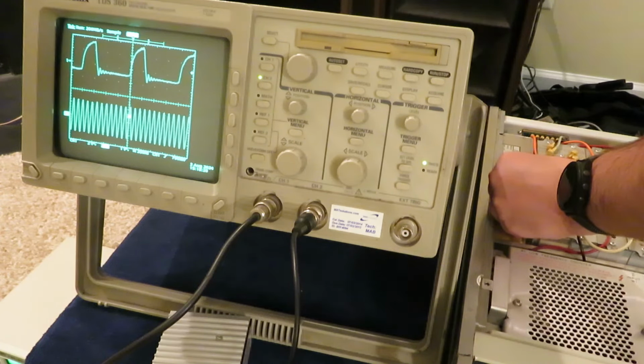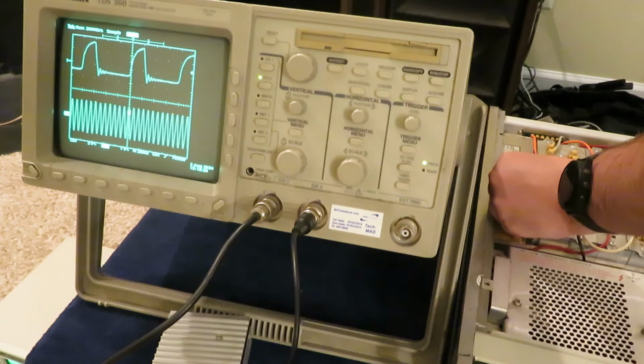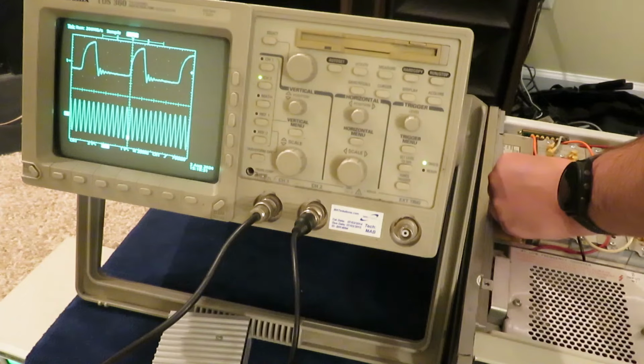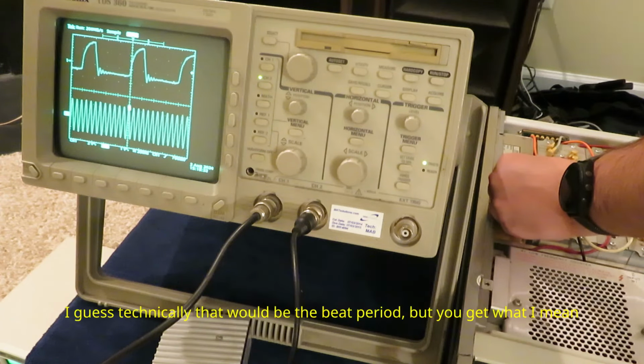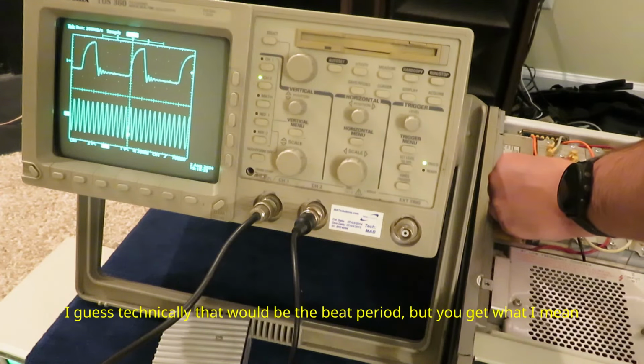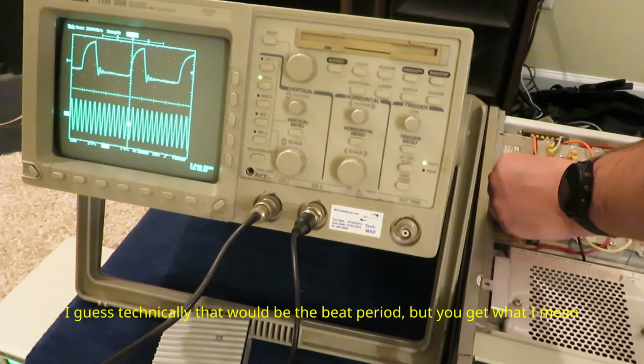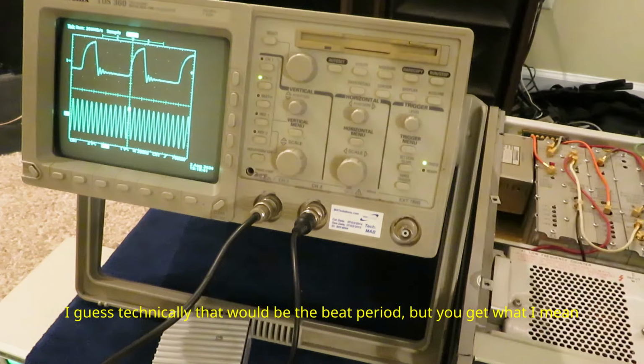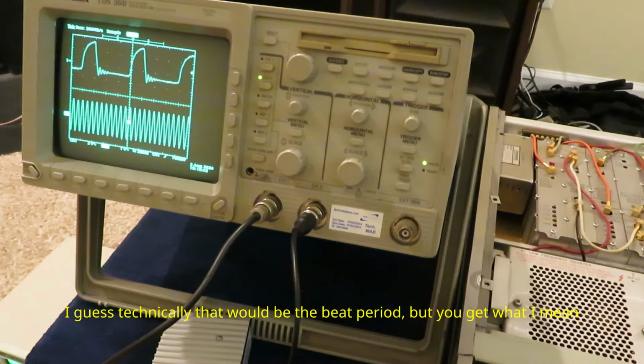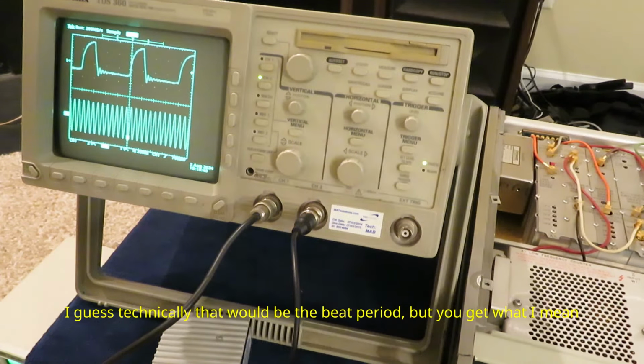So the test they recommend is, I think they said 5 seconds beat frequency, but because we're using a 10-to-1 ratio on our references, I think I'm just going to shoot for a half second beat frequency for one cycle on here to up here.